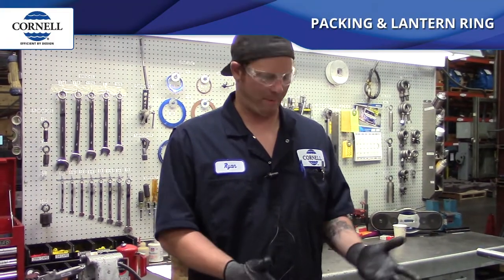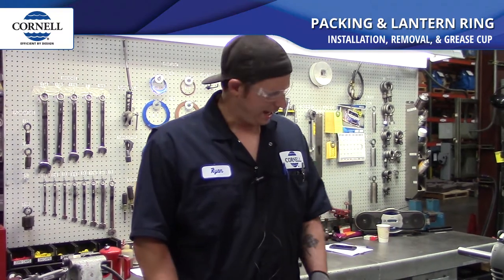Hey, I'm Ryan and I'm going to be going over some steps to put packing into a back plate. I'll also be talking a little bit about what purpose the lantern ring serves, what purpose the grease cup serves, and kind of show you how we do it here.